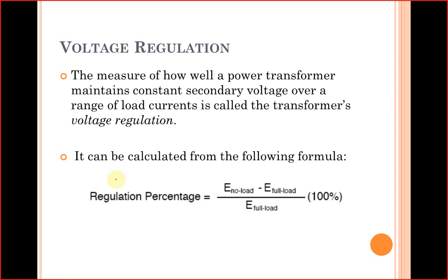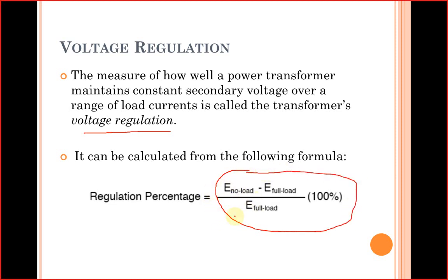We have already discussed voltage regulation in experiment number four. The measure of how well a power transformer maintains constant secondary voltage over a range of load currents is called the transformer's voltage regulation. In other words, the drop in terminal voltage when the transformer is gradually loaded is the percentage regulation. The formula is: voltage at no load minus voltage at full load, divided by voltage at full load, multiplied by 100.